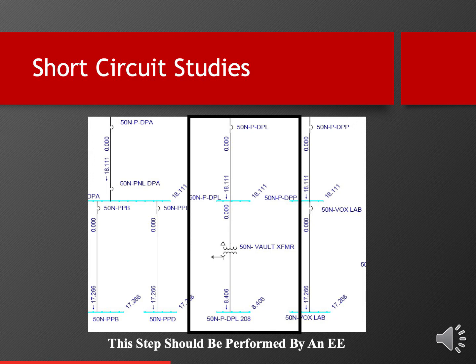It is important to recognize that the entire arc flash risk assessment study begins with the short circuit calculation from the utility company that feeds the plant. And so they will do a calculation usually on your incoming high voltage system, and then it would be incumbent on us engineers to take it from there down to the bottom of the study. So the short circuit calculations are very important, in particular to something called equipment duty, which we'll get to in a slide or two. This step really should be performed by an electrical engineer because sometimes there are some anomalies we'll get in the calculations, and it would really take an engineering eye to catch those. So this step really should be performed by an EE. Let's go to the next slide.